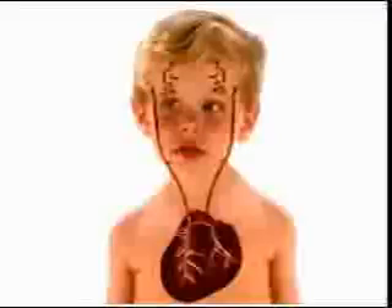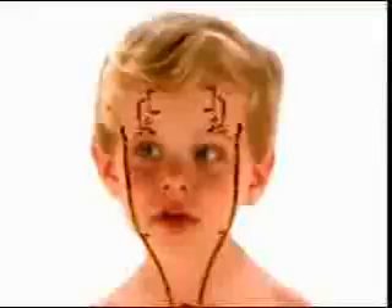Why the temporal artery? It's ideal for several reasons. First, it is located just a short distance from the heart. Also, it is readily accessible, lying just a millimeter under the skin surface of the lateral forehead. Moreover, because the temporal artery is highly perfused and has very little vasomotor activity, a steady flow of blood is assured. And with its terminal fork, the ability to obtain a correct measurement is doubly assured.